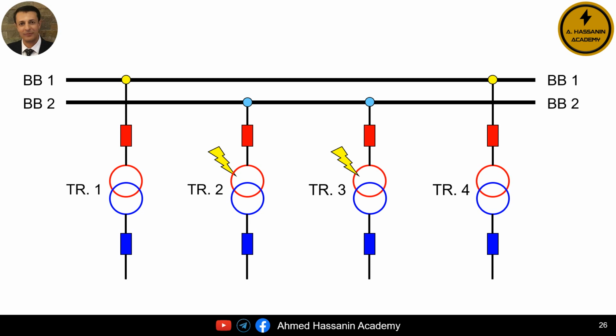energized, and supplying loads. This happens due to the DC component present in the magnetizing inrush current of transformer number 3. The DC component causes magnetic core saturation in transformer number 2 because it is either physically close to transformer number 3 or connected in parallel with transformer number 3. Of course, the magnetizing inrush current in this case is referred to as sympathetic magnetizing inrush current.